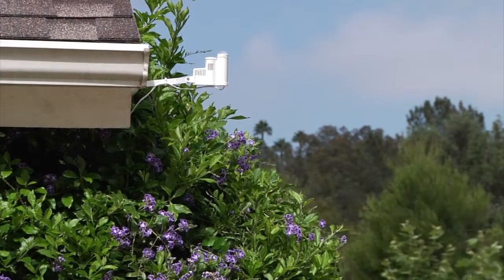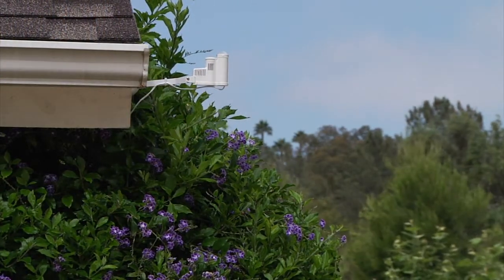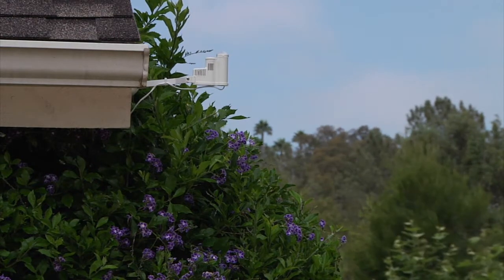So there's a few things to think about when you're considering a mounting location for your wall mount or your pedestal controllers. Of course, one of the main things is your power supply. Where do you have access to a switch or a circuit breaker within that area? Another consideration might be avoiding the direct sprinkler spray where possible, and or direct sunlight if you're able to. One of the other considerations might also be the proximity to your field wire and or your sensor wires. Where's your sensor going to go? Where is the field wire coming in from? So those will be things to think about.